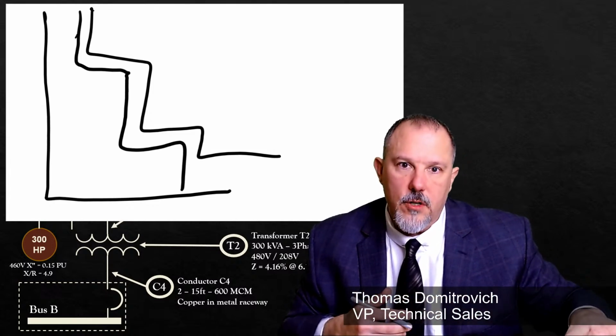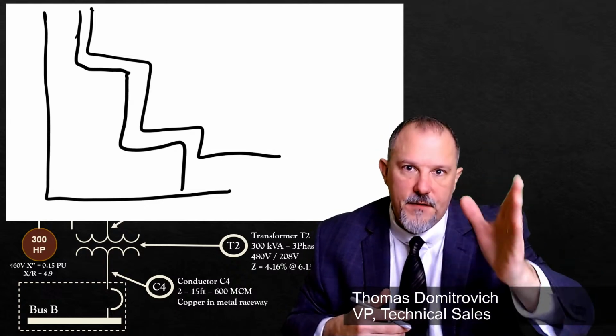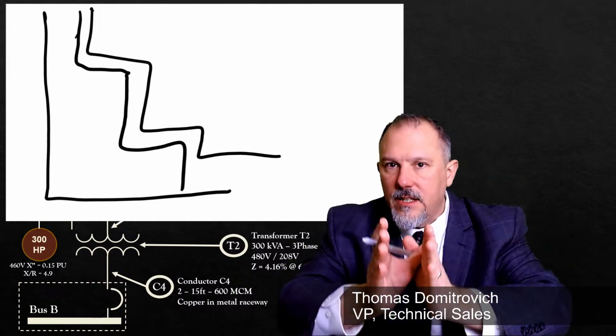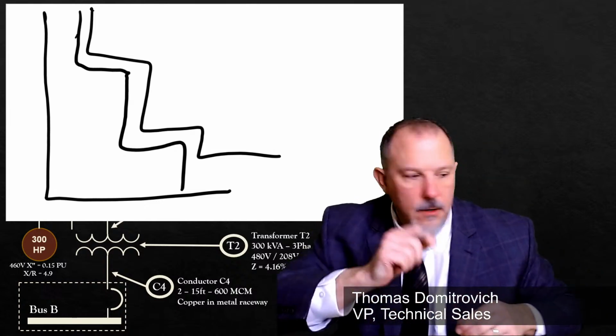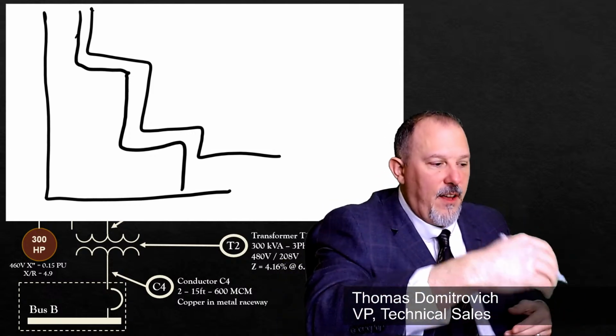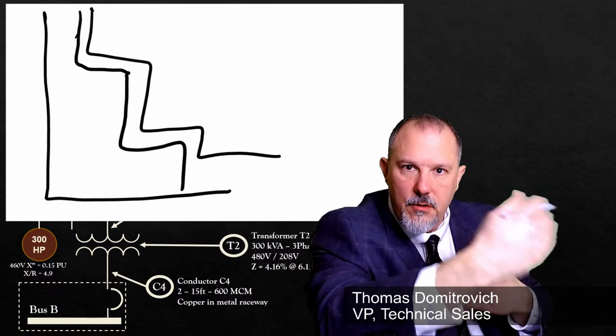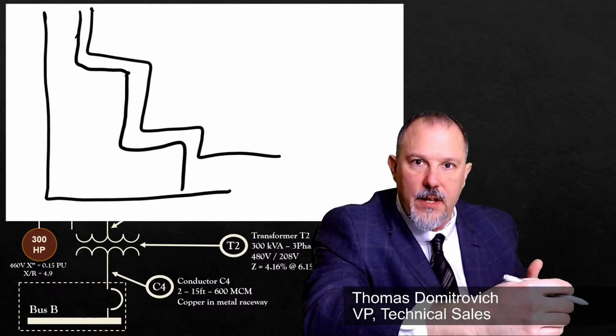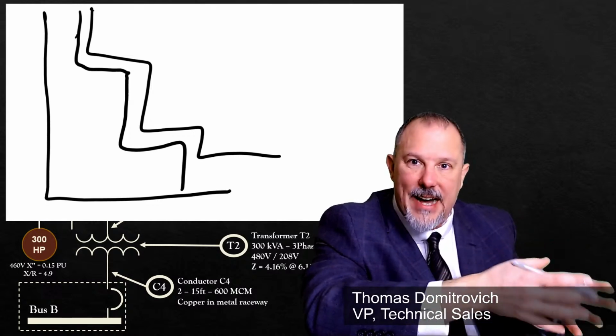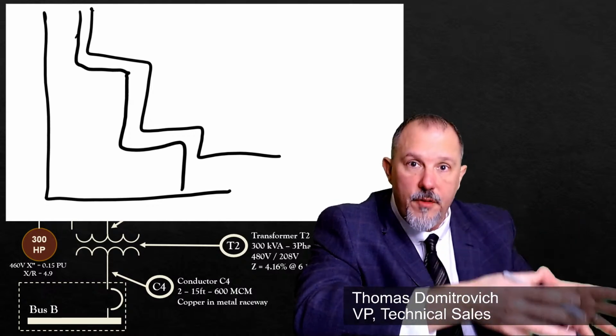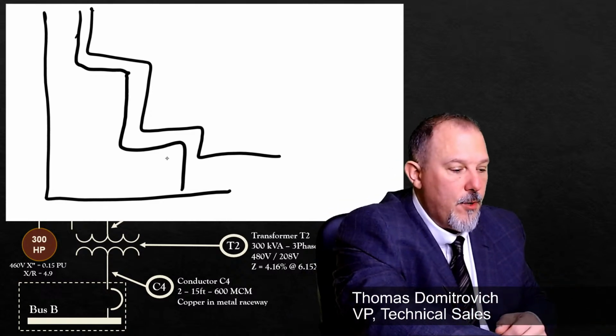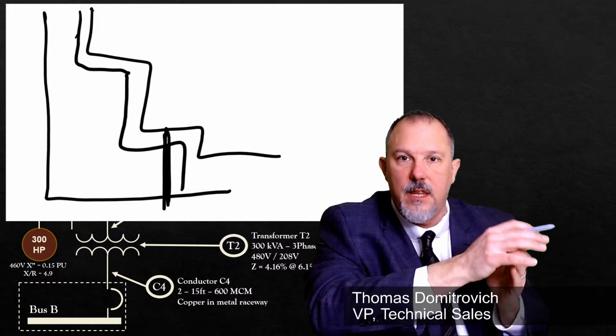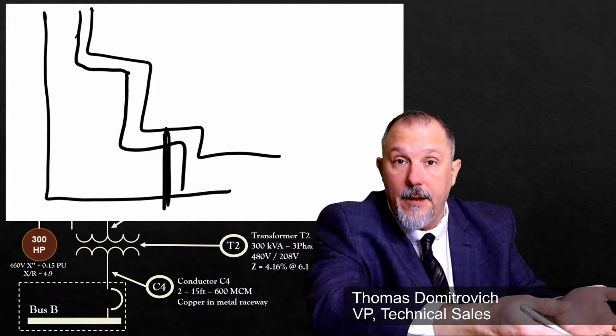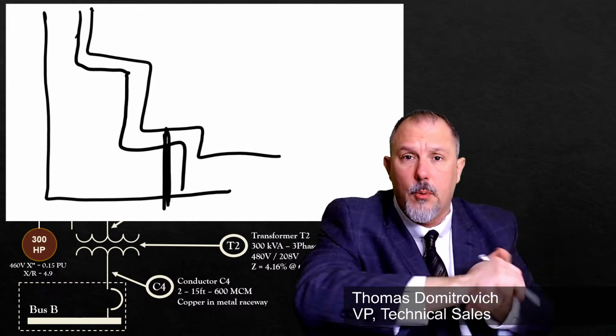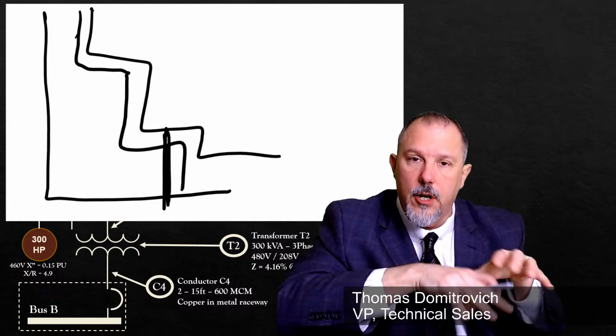This is what a trip curve looks like for an electronic trip unit. It's very defined. The bands are much tighter. Now, if this was that upstream 2000 amp breaker and I wanted to selectively coordinate and I wanted to keep my currents out of the instantaneous region of both devices, then I would know my 3-phase bolted fault current is in that region, which could be the short time delay region, which I can lower down to like 0.07 seconds and give you a good lower incident energy.